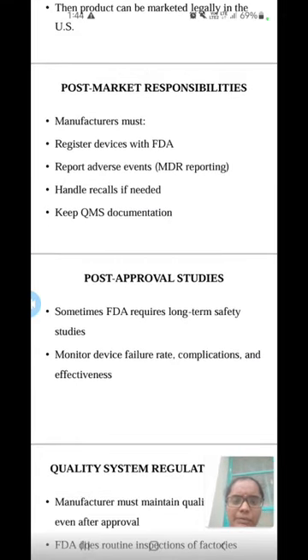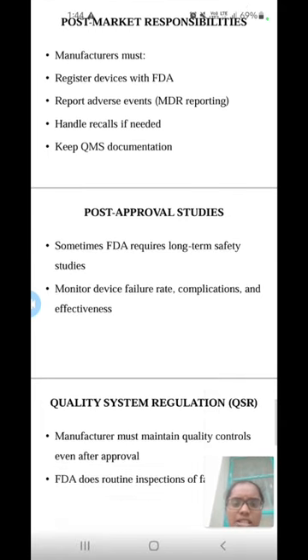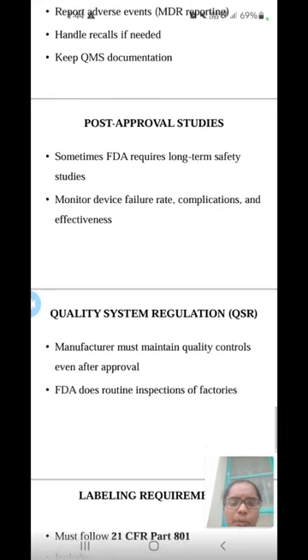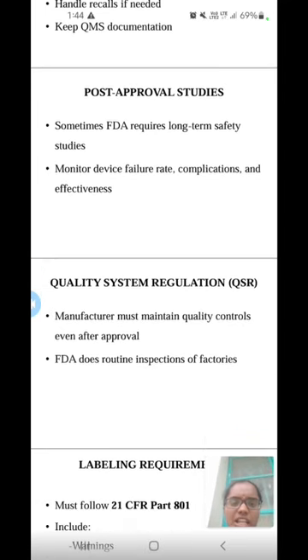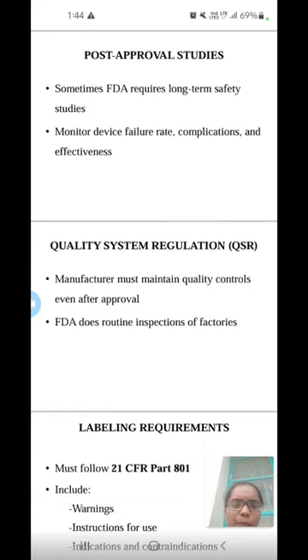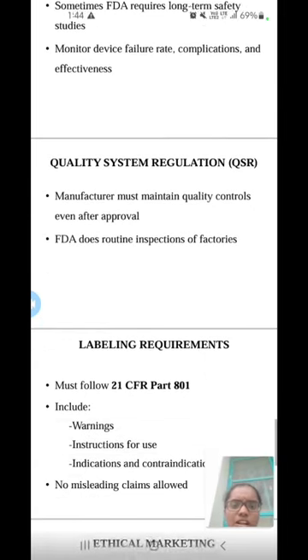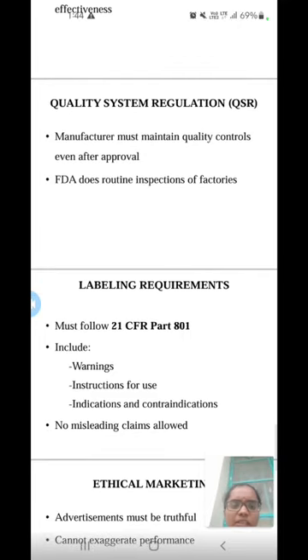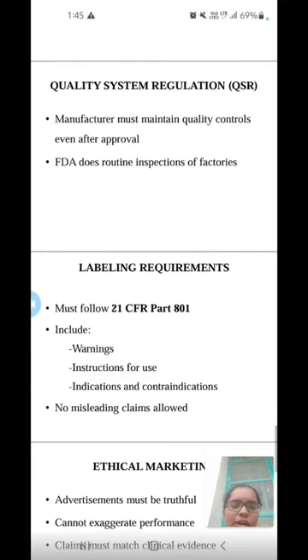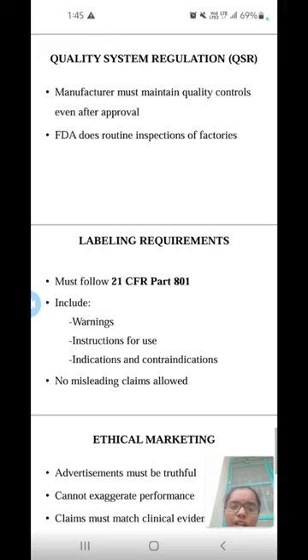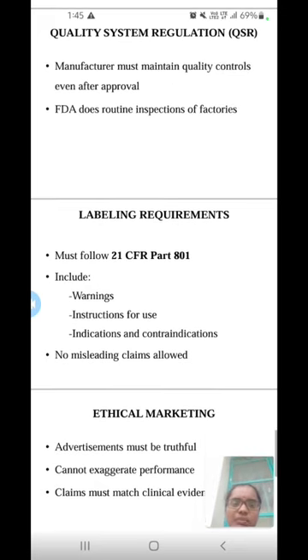Post-market responsibility. The manufacturer must register the device with FDA, report adverse events through MDR reporting, handle recalls if needed, and keep QMS documentation. Post-approval studies: sometimes FDA requires long-term safety studies to monitor device failure rate, complications and effectiveness. Quality system regulation: the manufacturer must maintain quality controls even after approval. FDA does routine inspection of factories.